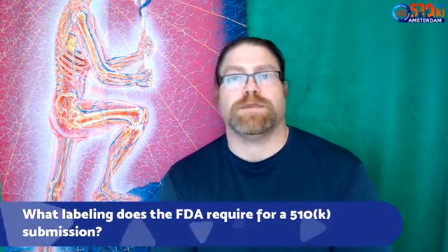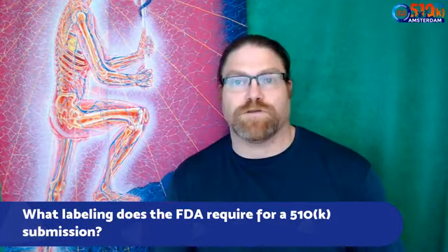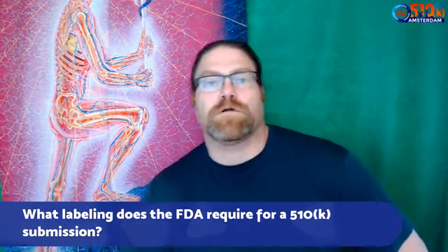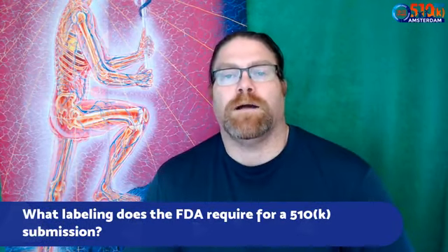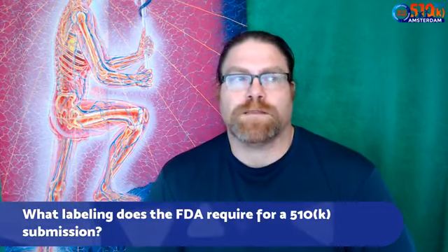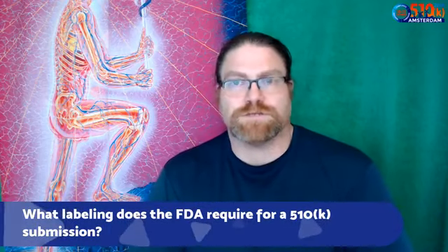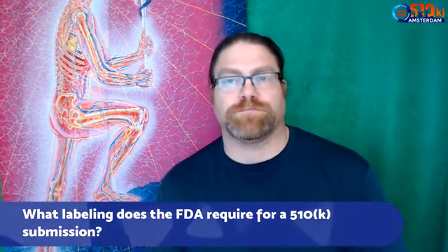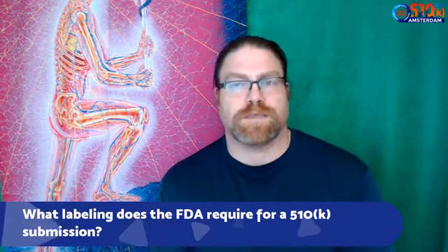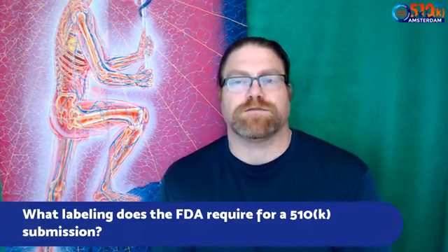So could you submit exactly what you submitted for your European CE marking for a 510K submission? Yes, in theory you could. There are a couple of challenges. Number one, you have to have an English translation. You can include the other translations with it, but the FDA only accepts English. So as long as the English is with all the other languages, that's okay.